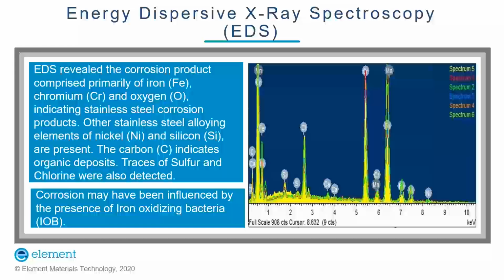EDS analysis found that the corrosion may have been influenced by the presence of iron oxidizing bacteria, as large amounts of iron oxides were detected. The presence of sulfur in the deposit may have been linked to the presence of SRB bacteria as well, which is known to cause pitting corrosion in steels.